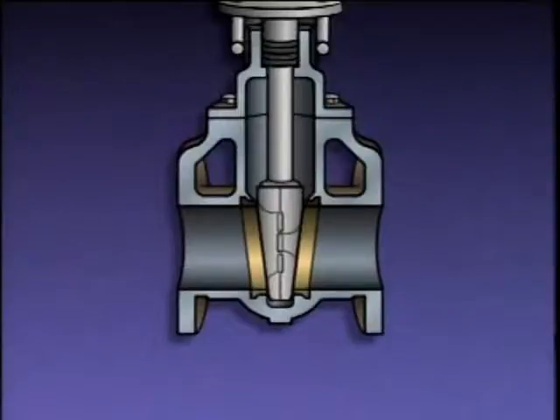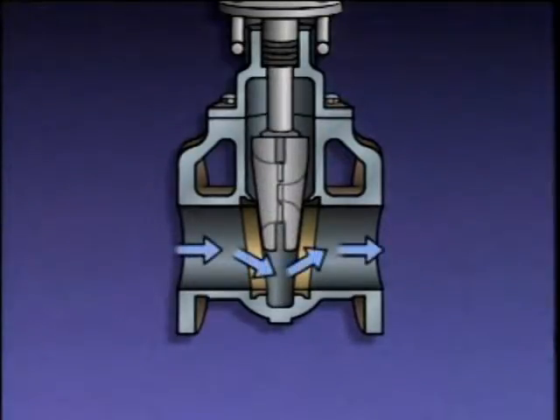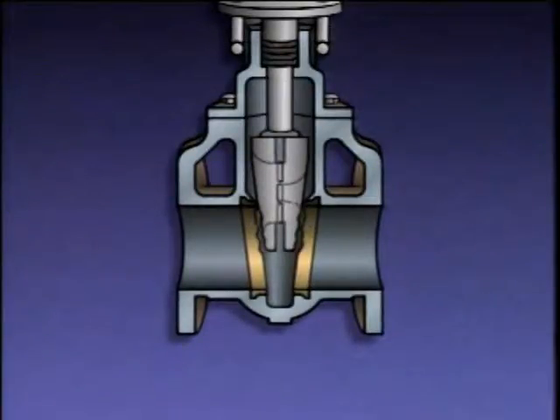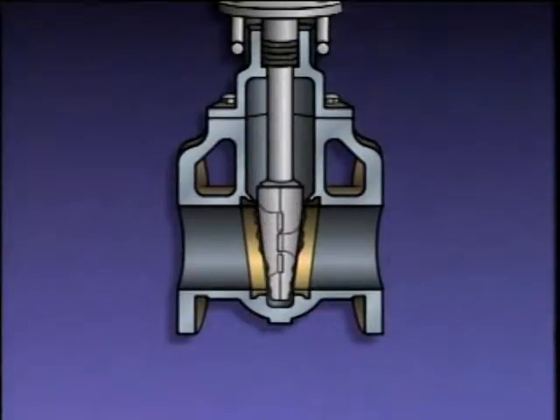Gate valves are normally used in on-off applications, but in an emergency they can be used to throttle flow. However, long-term use as a throttling valve can damage a gate valve. When the disc is raised slightly, fluid flow creates turbulence, which causes the disc to swing from side to side, banging or chattering against the seat. This chattering causes wear on the seat and disc, and eventually the valve will not shut off flow when completely closed.